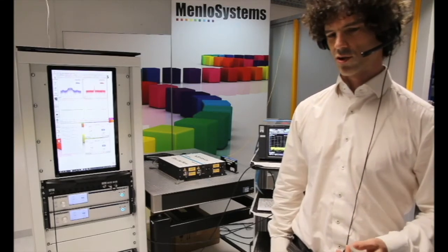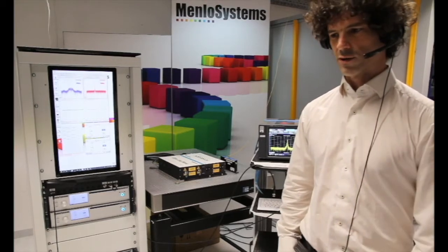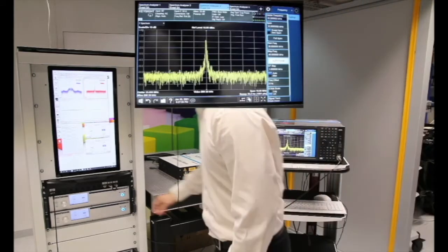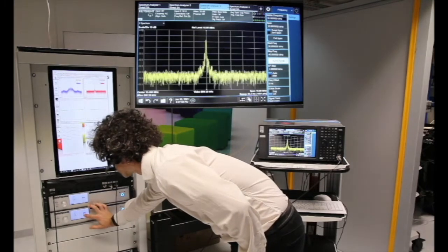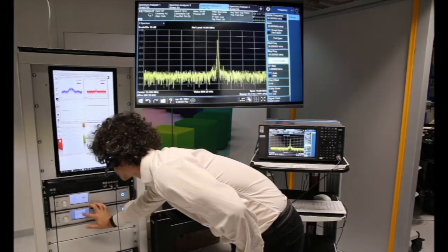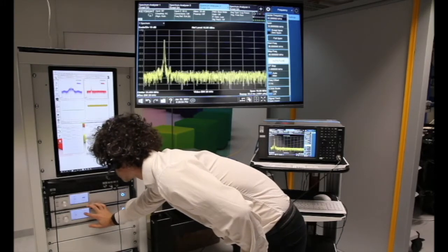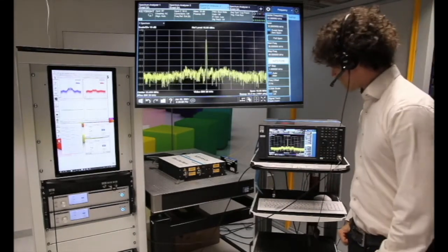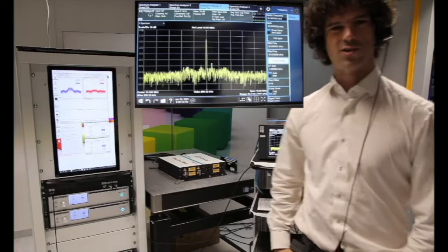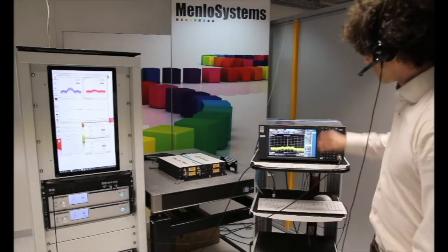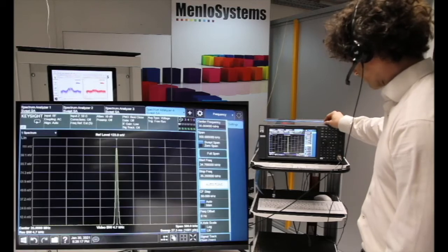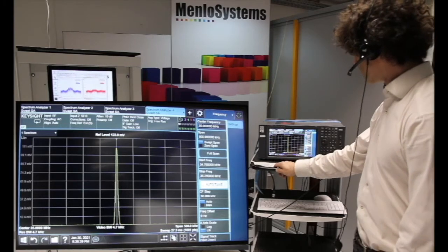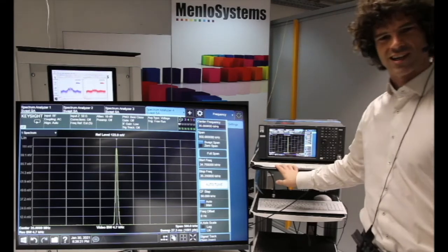If you want to reduce the linewidth, you can also apply the optical lock. This means we will not lock our comb to the RF reference — instead we will profit from a good CW laser and lock our comb to that system. To do this it's quite simple: we unlock the system, load the optical lock settings, and activate the lock. The linewidth shrinks down significantly. Going back to the linear scale with a 500 kHz span, we see we are limited by the resolution of our spectrum analyzer.